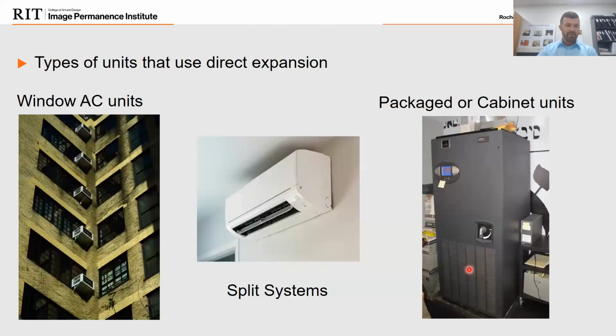And here are some examples. Those window style units you see. Even the split systems that a lot of institutions have, we've seen these, a lot of historic buildings have actually started installing some version of these. What is inside your space is the room side of that unit, and then your refrigerant literally pumps the heat all the way outside to the condenser, and then that condenser is going to reject that heat and then pump the new refrigerant back to the unit. And some of these package units also operate the same way, depending on the style of package unit you have.